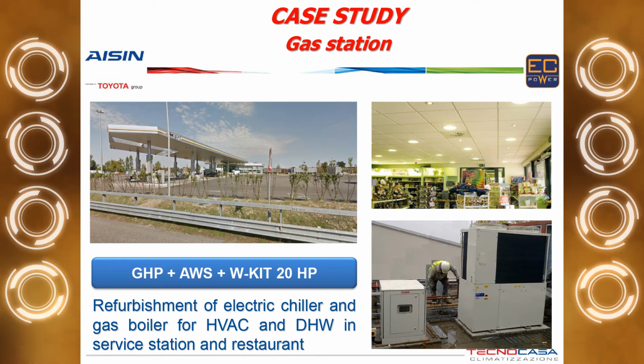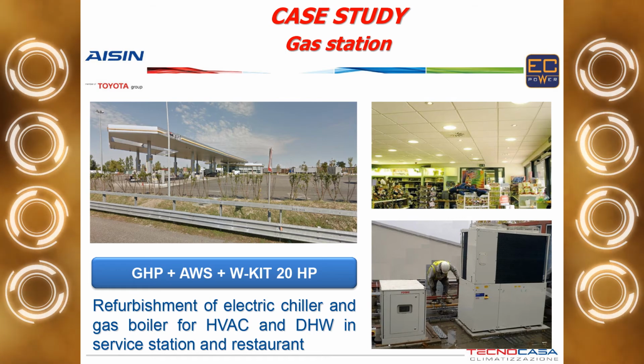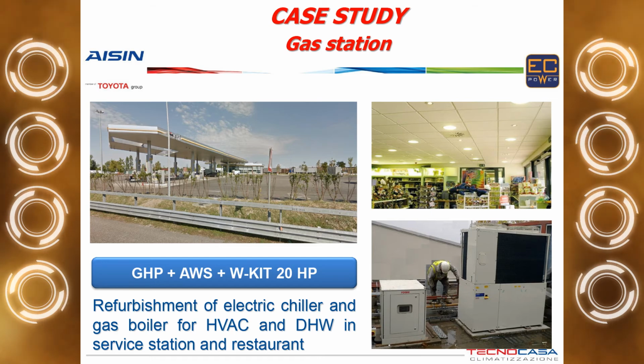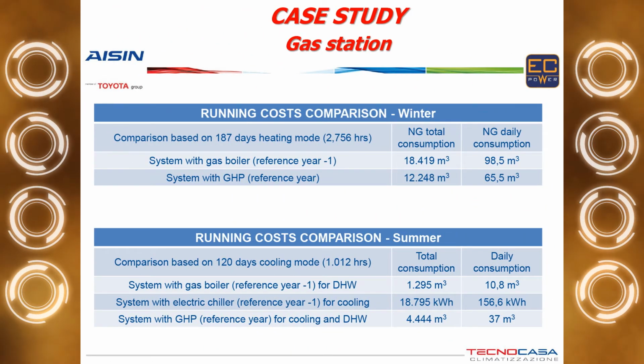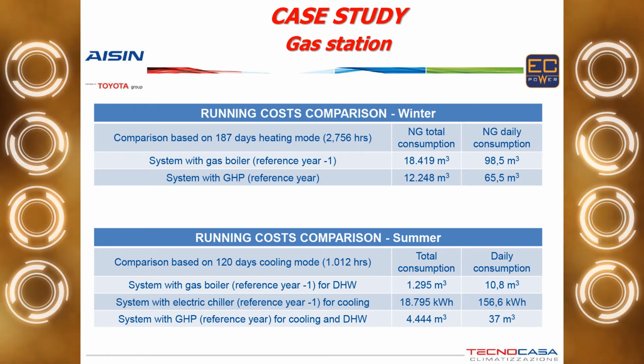So in winter, we made a comparison based on 187 days heating mode, something like 2,800 running hours. So the system with gas boiler needed 18,419 cubic meters for the whole reference period, which meant almost 100 cubic meters per day in the consumption. The year after, when the GHP was installed, we had a gas consumption of 12,248 cubic meters, which means 65.5 cubic meters per day.